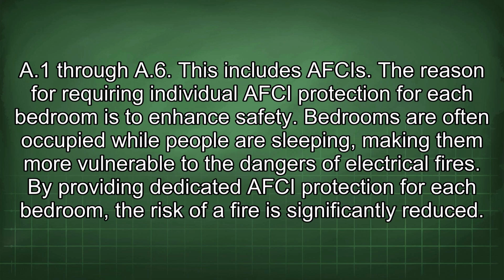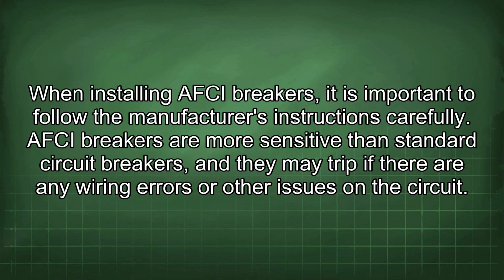Bedrooms are often occupied while people are sleeping, making them more vulnerable to the dangers of electrical fires. By providing dedicated AFCI protection for each bedroom, the risk of a fire is significantly reduced. When installing AFCI breakers, it is important to follow the manufacturer's instructions carefully. AFCI breakers are more sensitive than standard circuit breakers, and they may trip if there are any wiring errors or other issues in the circuit.